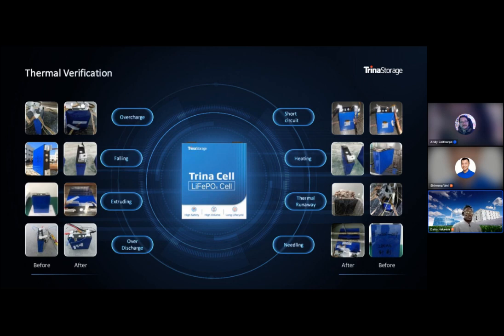Think about UL 1973, for example, that Shimeng showed earlier on. What we tend to do is put a normal cell, or a normal device under test, into an abnormal condition that could realistically happen - short circuit, dropping - what's going to happen? Does it spontaneously combust? We definitely don't want that. We then do that test, confirming it doesn't combust based on realistic abuse conditions it could face in real life.